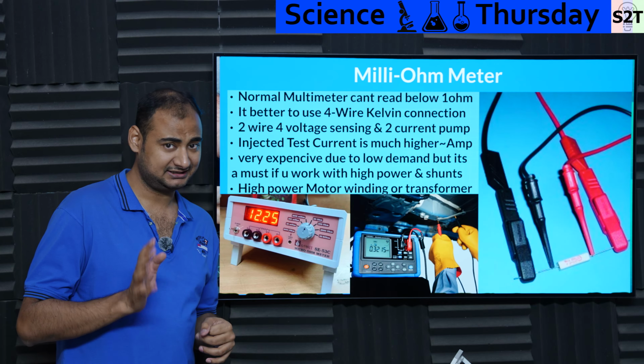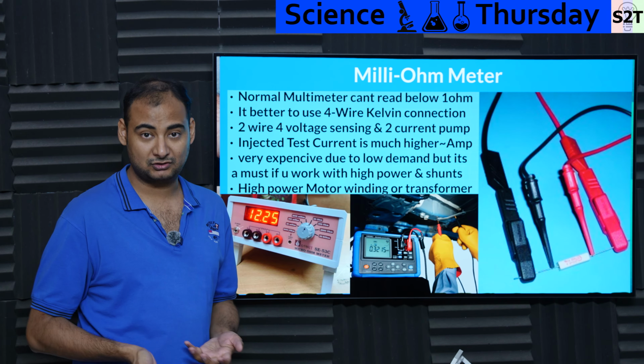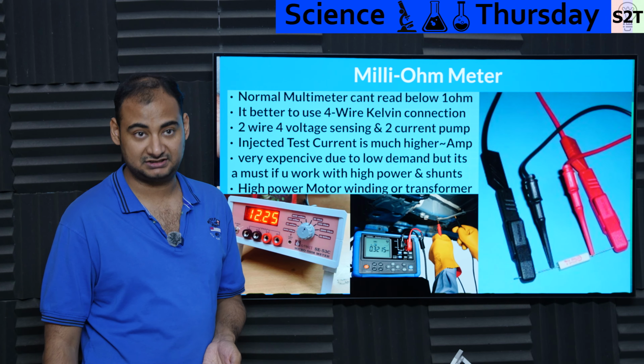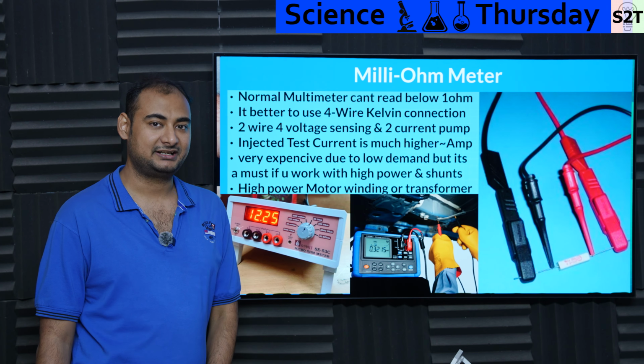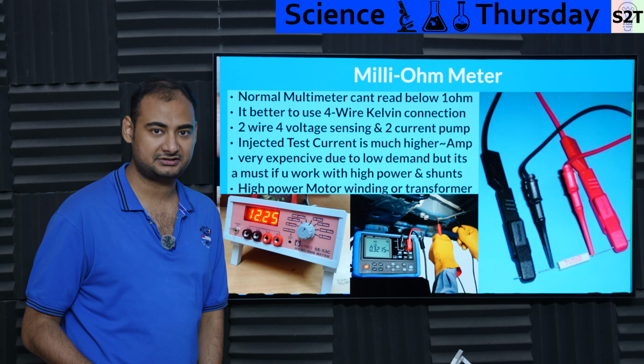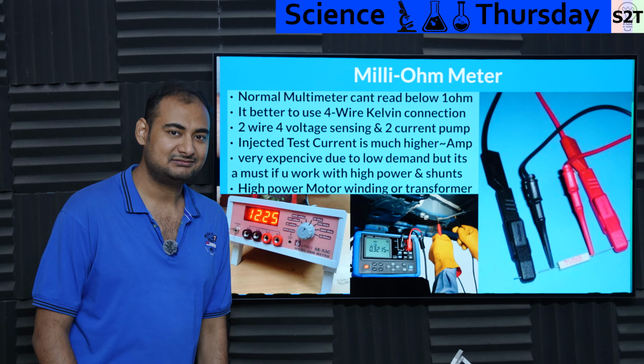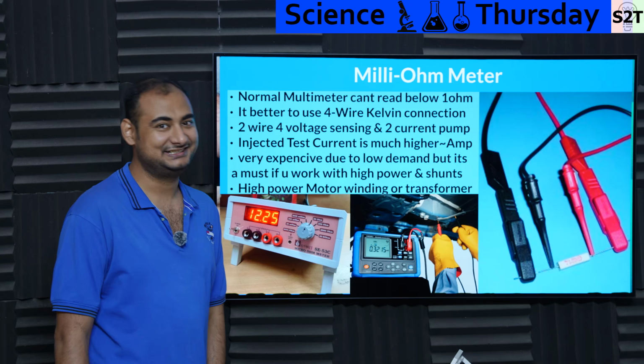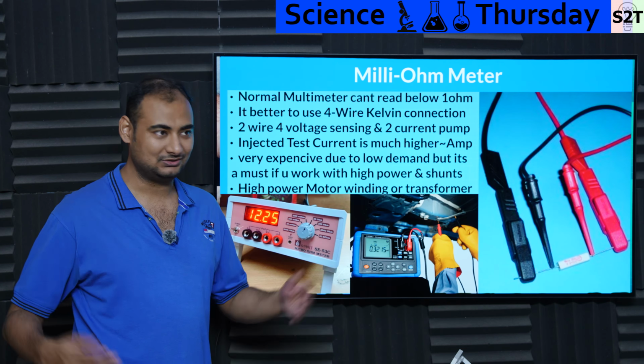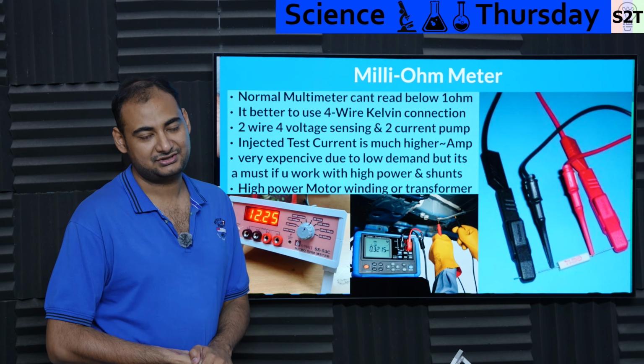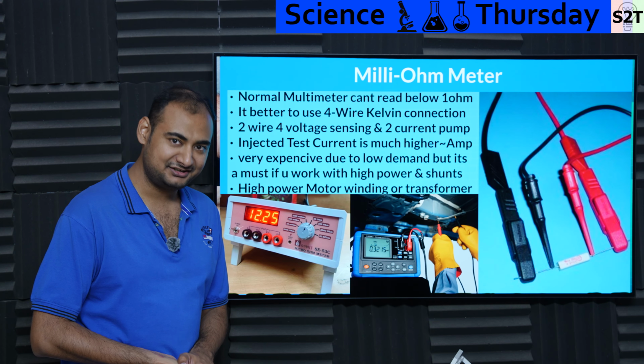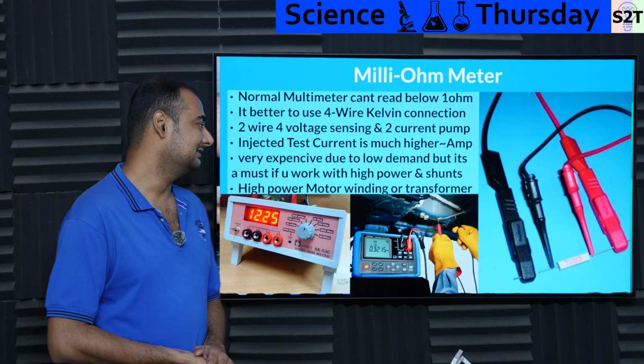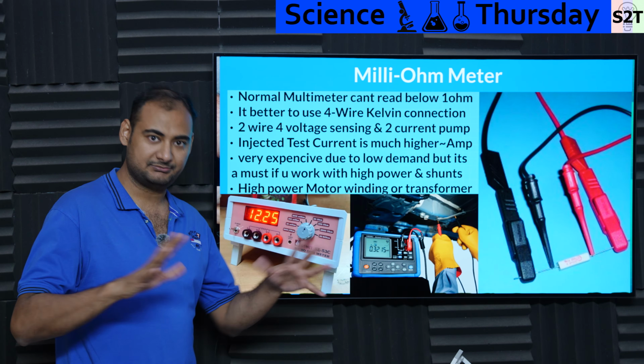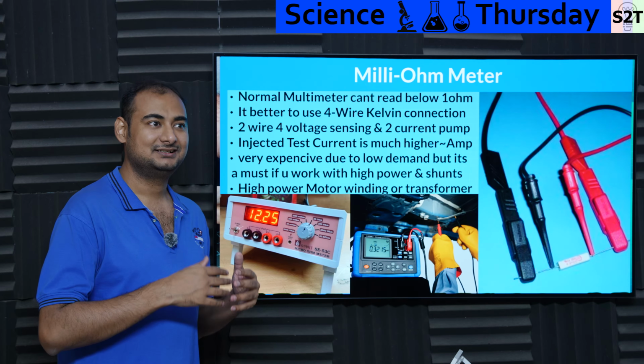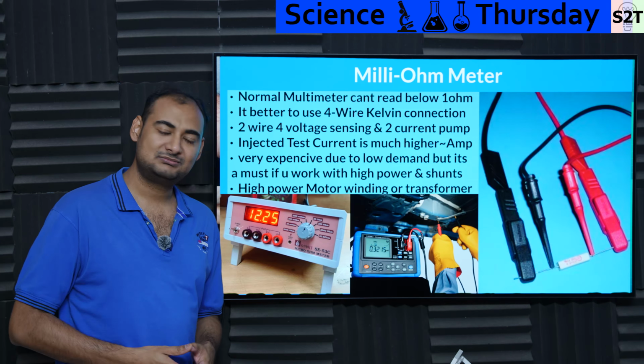Even though it's necessary, there are certain fields where it's becoming more and more necessary. For example, if you're working with electric vehicles, how do you know the motor coils are healthy? Right now everybody tests the insulator, but what about the conductor? Is it healthy or not? If you're dealing with a transformer, you measure if the insulation is intact, but what about the conductor? Conductor also ages, so fundamentally, is it in balance or off balance? You have to measure that, and a normal multimeter will not cut it.